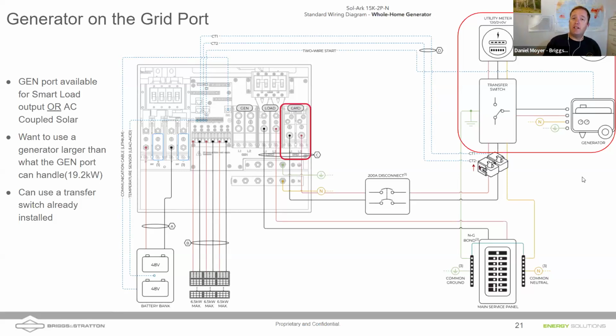Yep. This, I think, is a great example of how you can come out to a house that maybe already has an existing generator and an existing transfer switch, and not really have to rip any of that off the wall. Exactly. We leave the transfer switch in place, right? So if the grid goes down, the generator is going to recognize the loss of utility. It's not going to start, right? Because it's still waiting for that 2-wire signal to start. We're not going to use the automatic grid-sense start of the generator. We're still going to use the 2-wire start, and so the batteries power loads first. But if they get down, they can send that signal to the generator.